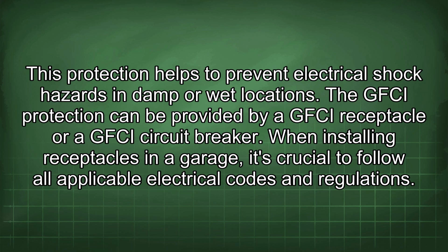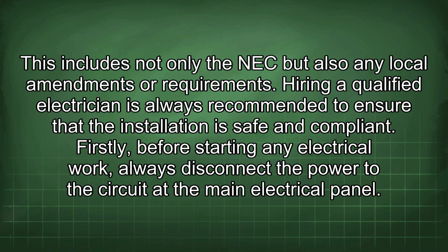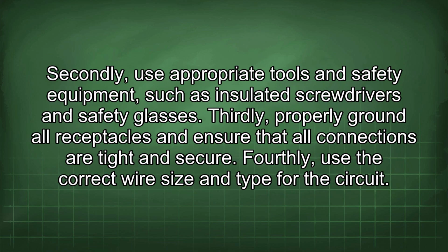When installing receptacles in a garage, it's crucial to follow all applicable electrical codes and regulations. This includes not only the NEC but also any local amendments or requirements. Hiring a qualified electrician is always recommended to ensure that the installation is safe and compliant. Firstly, before starting any electrical work, always disconnect the power to the circuit at the main electrical panel. Secondly, use appropriate tools and safety equipment, such as insulated screwdrivers and safety glasses. Thirdly, properly ground all receptacles and ensure that all connections are tight and secure.